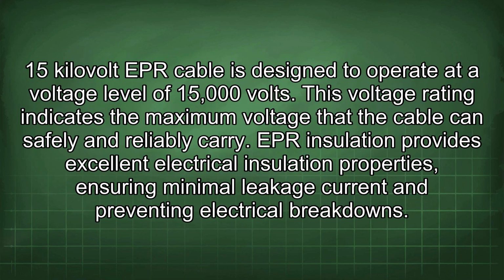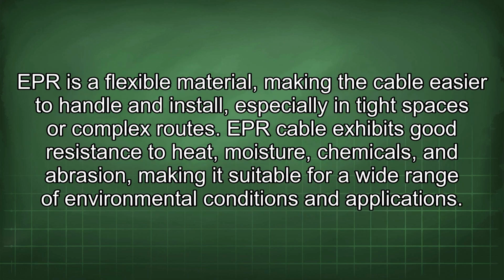15 kilovolt EPR cable is designed to operate at a voltage level of 15,000 volts. This voltage rating indicates the maximum voltage that the cable can safely and reliably carry. EPR insulation provides excellent electrical insulation properties, ensuring minimal leakage current and preventing electrical breakdowns. EPR is a flexible material, making the cable easy to handle and install, especially in tight spaces or complex routes.